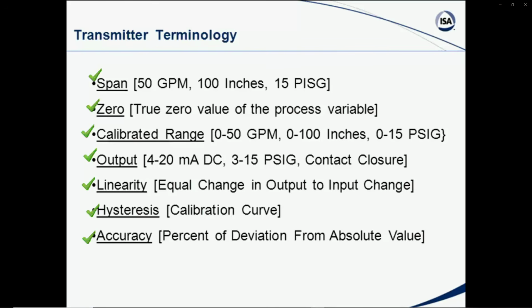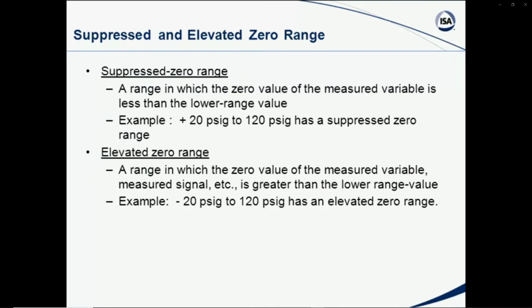And then the base term of accuracy, which is really simply the percent of deviation from the absolute value. So these are some terms that you will see with respect to any kind of a transmitter, regardless of the particular process variable that you're dealing with. Some other terminology that you might see or run into on the exam or in your work is a term called the suppressed zero range. That simply is a range in which the zero value of the measured variable is less than the lower range value. You're looking at true zero and comparing it to the lower range value. If it's less than that, it is a suppressed zero range.